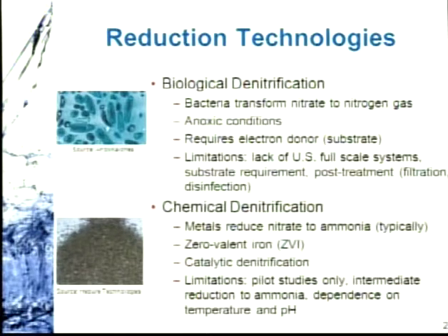water utility systems. You have to supply a substrate here. You have to provide an electron donor, so you're either adding acetic acid, or there are other examples that will be presented this afternoon. Sometimes you can use hydrogen as an inorganic donor. Those are chemical supplies that would need to be delivered to those treatment systems on an ongoing basis, and so we want to compare those approaches with other technologies that might be offered as well.